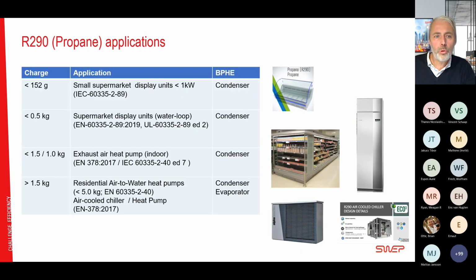Some words about propane applications. For systems with a charge below 152, you can basically place them anywhere, and you do not need to take huge precautions for these. Here we see small display units in supermarkets. Quite often they are air-cooled, but we also see water-cooled, and here BPHEs are used as condenser. You can see one example here, for example.